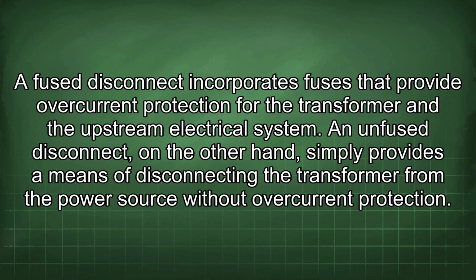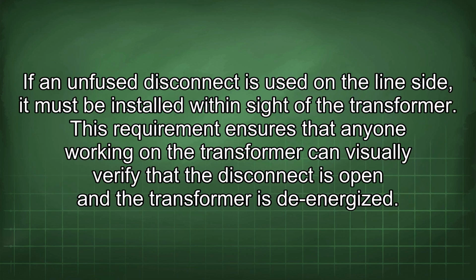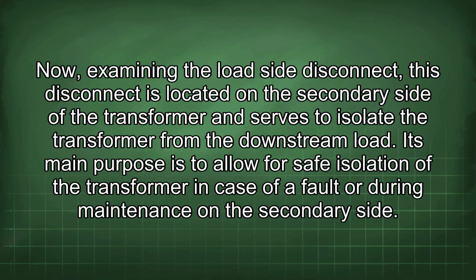A fused disconnect incorporates fuses that provide overcurrent protection for the transformer and the upstream electrical system. An unfused disconnect, on the other hand, simply provides a means of disconnecting the transformer from the power source without overcurrent protection. If an unfused disconnect is used on the line side, it must be installed within sight of the transformer. This requirement ensures that anyone working on the transformer can visually verify that the disconnect is open and the transformer is de-energized. Now, examining the load side disconnect.